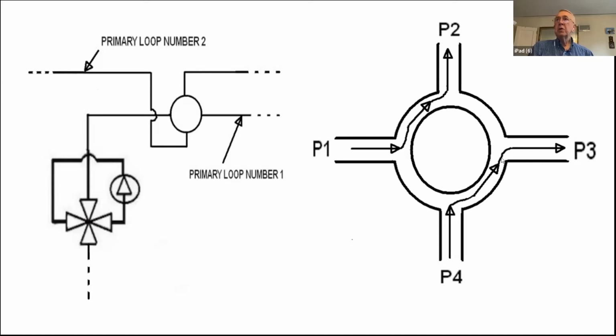So basically, the way this works is when we have an equal flow rate in those 2 primary loops, then all of the water from primary loop number 1 has to flow into primary loop number 2. It cannot flow in directly across. It has to flow all the way through primary loop number 2, and then it comes back and gets back into primary loop number 1. So if you have a molecule of water that you're trying to follow through both of these loops, it's going to go through both loops before it can get back to where it started.